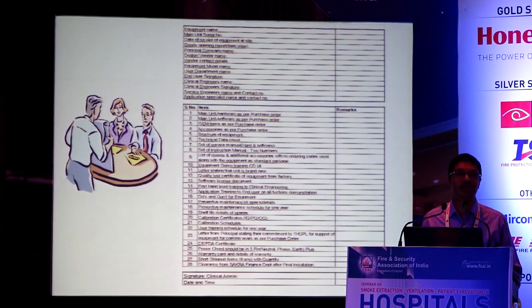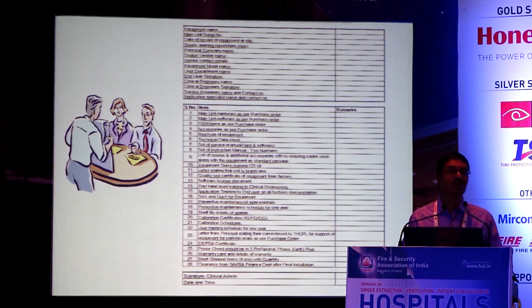But till then, what needs to be done? We need to have a proper pre-commissioning check for medical devices. Very important. If you don't take all these inputs, you may end up in a situation where the device is partially functional, does not have the safety features, or has not been properly commissioned. There are instances in third world countries where the same model of equipment sold abroad is sold at a lower cost, but it may be refurbished or some compromise has happened. So it is very important from a hospital perspective that an equipment pre-commissioning checklist is there and is ensured as part of your sales agreement, so that you can be sure the commissioned equipment is safe to use.